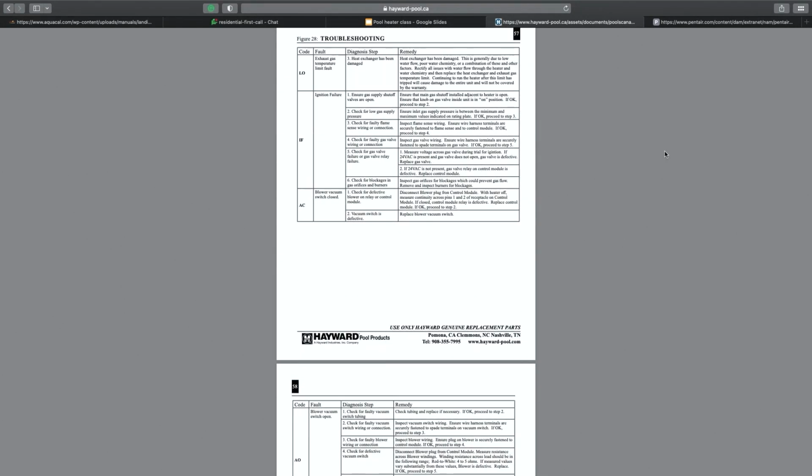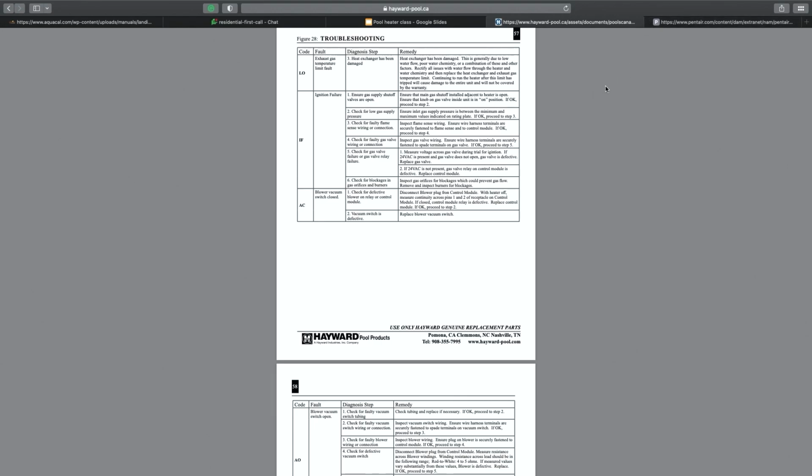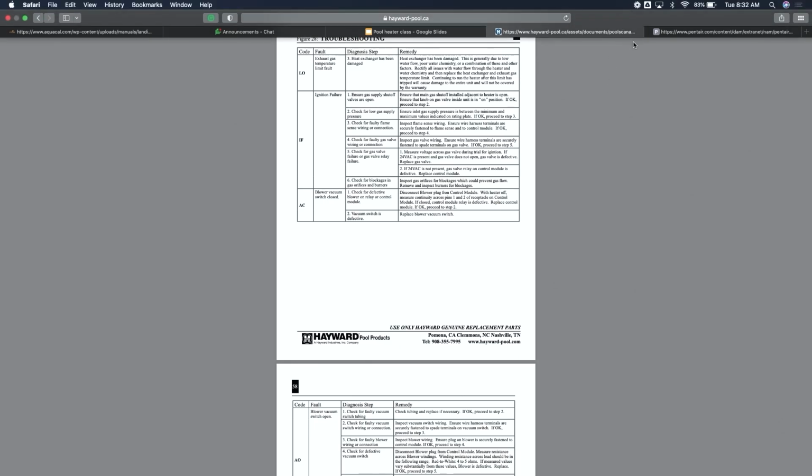I was helping Sean yesterday on a pool heater that is a lot more rare, the Jandy gas heater. And so neither of us really remembered how to access the blower wheel and all that. And I pulled it up and he was taking it apart at the same time. He found it before me, but in the install manual, just a full disassembly of each one of these parts and how to get to it when you need to get to something like a stuck blower wheel. So that's not control specific, but I just want you guys to get familiar with busting out these install manuals and going through the heater that you're struggling with. It's going to have what you need on there.